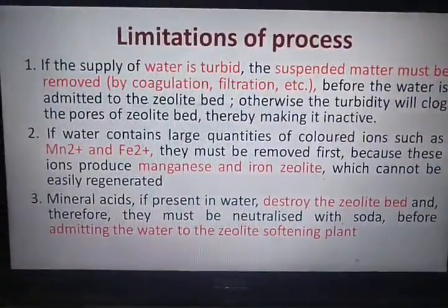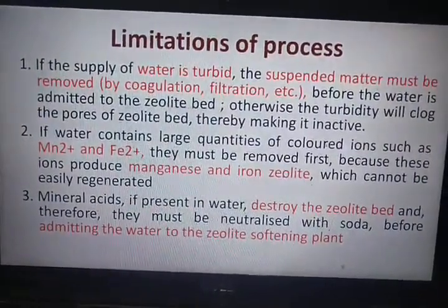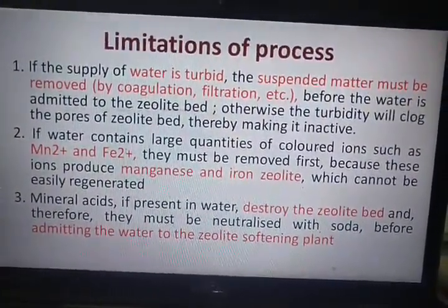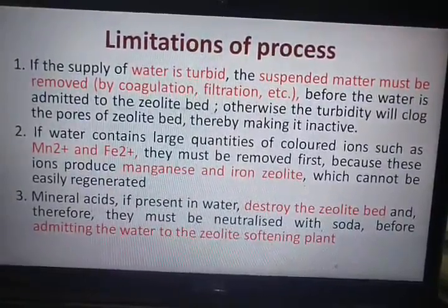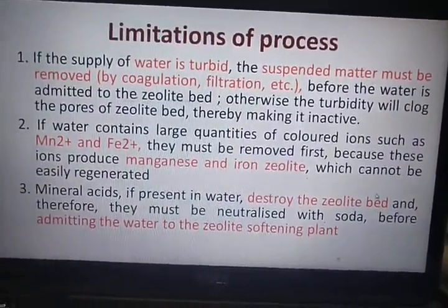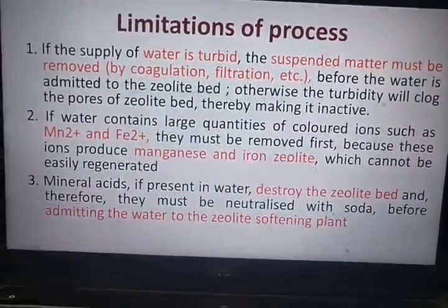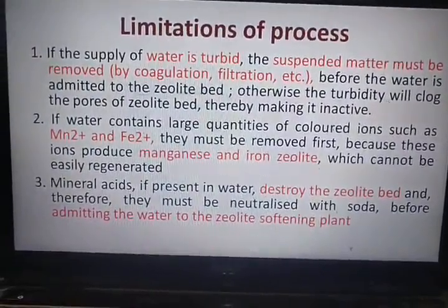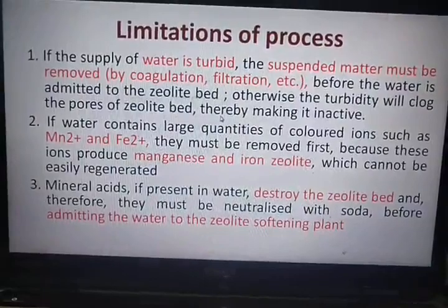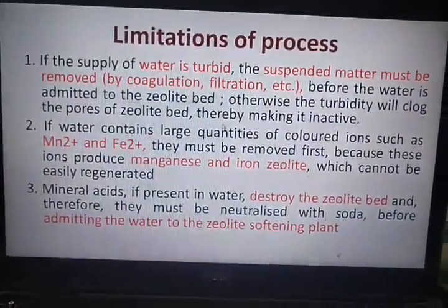So these are some of the limitations of the zeolite process. If the supply of water is turbid, the suspended matter must be initially removed, that is with the process of coagulation and filtration. This needs pre-treatment before the water is admitted to the zeolite bed. Otherwise the turbidity or the suspended solids present will block the pores of the zeolite bed, thereby making it inactive, and the hardness removal efficiency gets reduced.